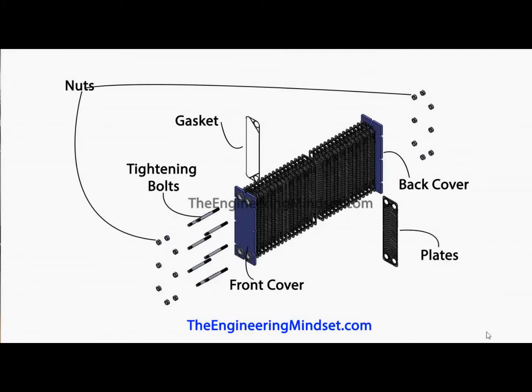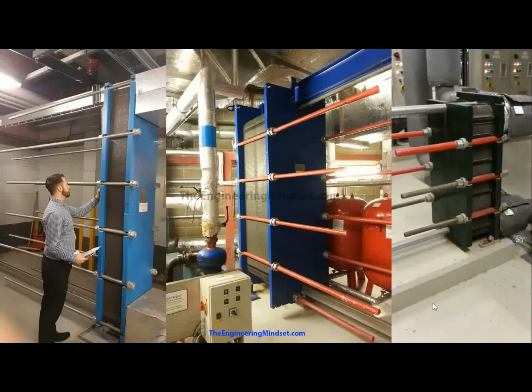Wedged in between there, we've got the plates where the heat transfer occurs, and the gaskets which sit between the plates, giving it the seal. Larger heat exchangers will also have a supporting bar at the top and bottom, and the case and plates just slide along there. There are various ways they can come off: either they twist off, though these ones would be too big to twist, but there's a section removed at the back where they'll just drop out. The smaller ones will just slide in and out.